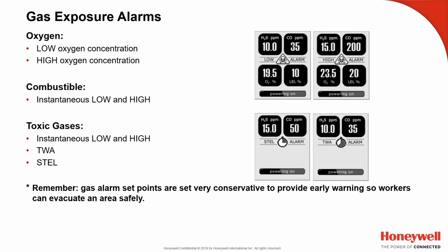Based on your province, what you'll find is that the TWA is typically one and done. You get a TWA alarm, say for example, in Canada, the recommendation or requirement is 25 ppm CO for an 8-hour day, and that's the average, which means that if you double that and you hit 50, it will cut in half the time that you can work in that confined space.